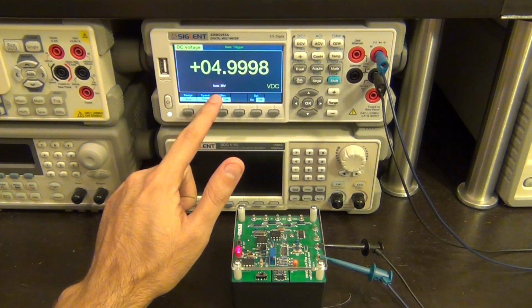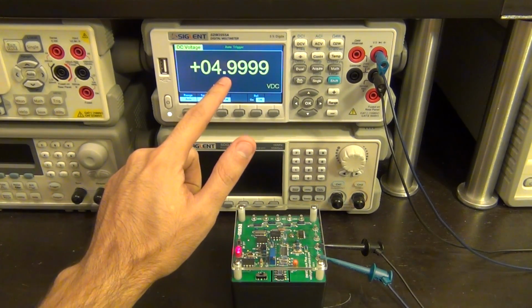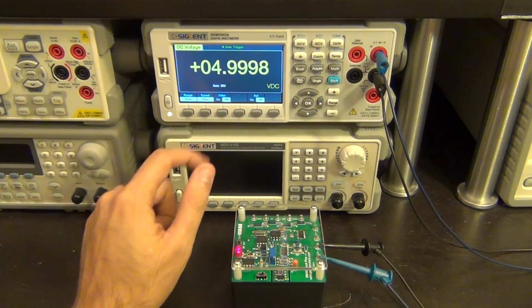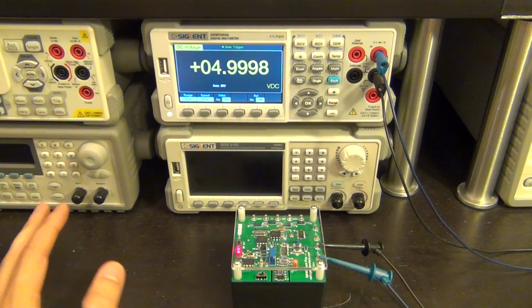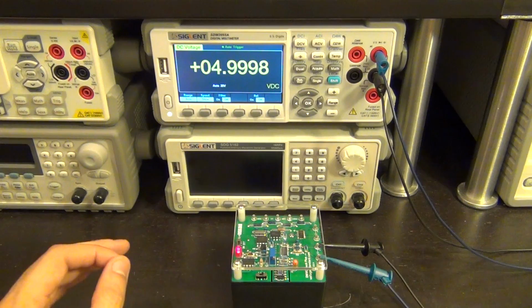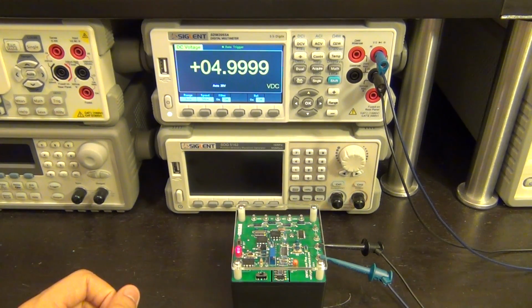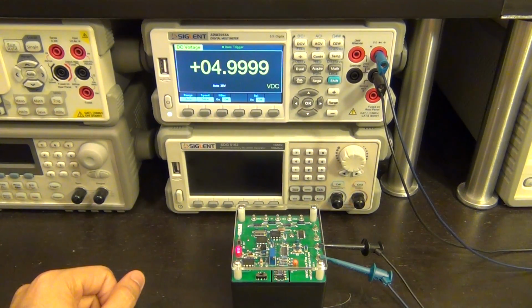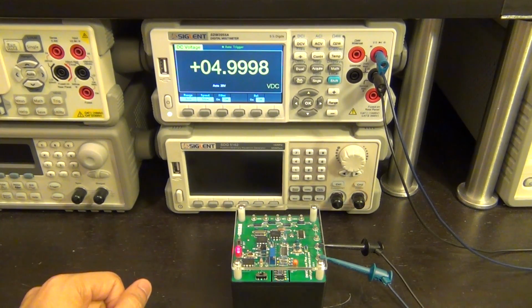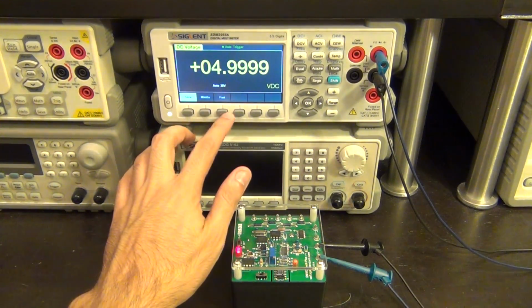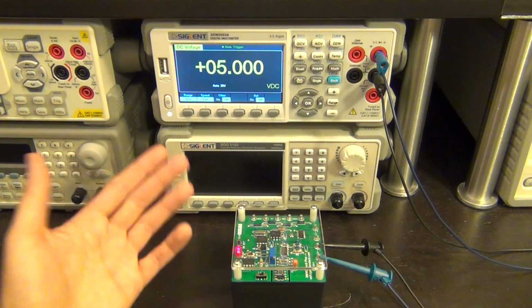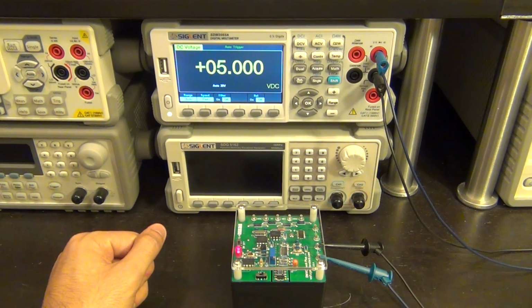So you can see it jump to 20 volt, and it says 4.9999 or 9998, which is extremely accurate. That's exactly what it should be. In fact, the reference is just a little bit below 5 volts based on my last measurement. You can see that it is essentially correct, and it's very, very accurate. And of course, it doesn't matter if I change the speed to fast. It's just going to lose a digit, but then it rounds up to a 5 volt value.